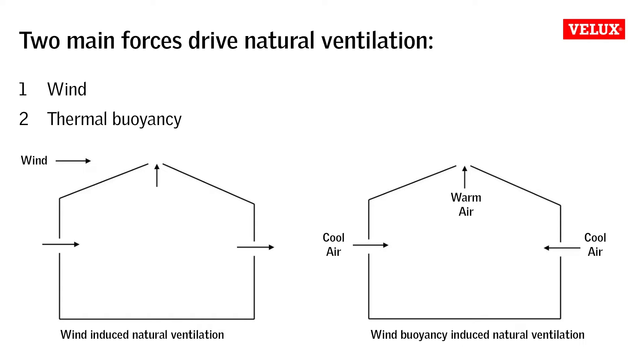Let's first have a look at the natural forces at play which drive natural ventilation. Natural ventilation is regulated by the pressure differences between inside and outside. These differences are mainly induced by two phenomena: wind, which creates positive pressure on the exposed facade and negative pressure on the opposite facade, and the difference in temperature in the building causing thermal buoyancy, allowing the denser cold air to lift warmer air up and out of the building.